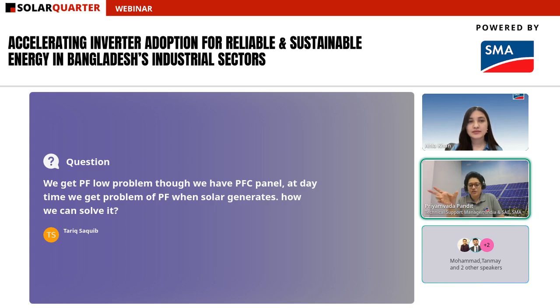There's still a limitation - there's a window within which the APFC panel can control. If your PV system is considerably large, it might go outside that window, and that's why it isn't able to recover the power factor. So you can get help from the solar generators, which will supply reactive power whenever required, so that your PF at the grid interconnection point is maintained.